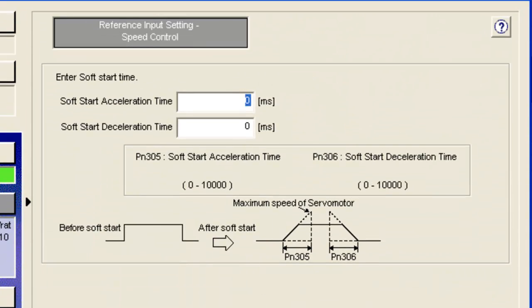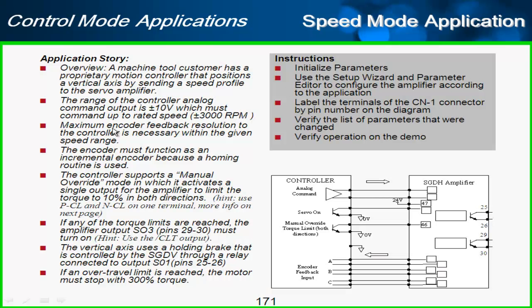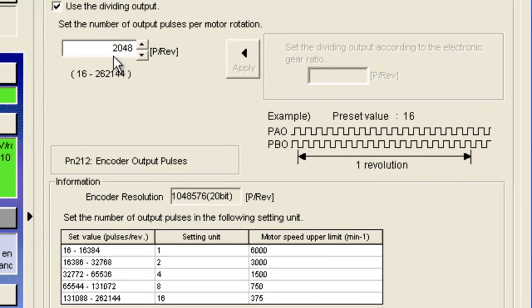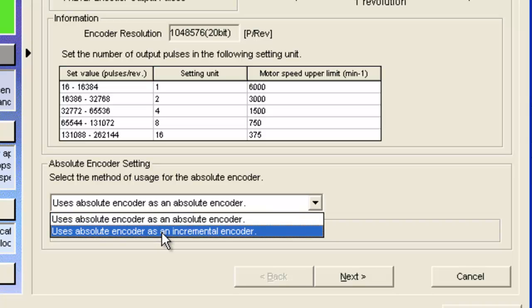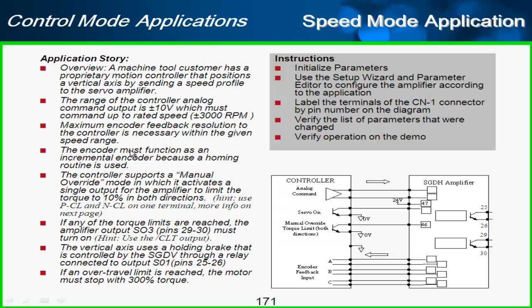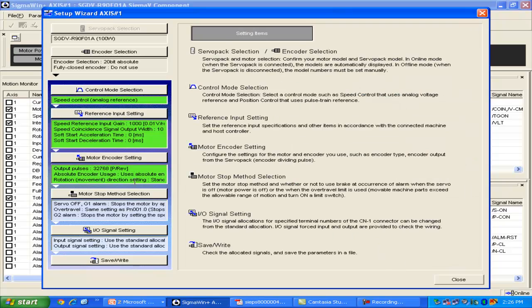There was no mention of a speed coincidence or V-comp output, so I'll click next. There was no mention of any acceleration times, so we'll leave those at default. On to motor encoder setting — this is the number of pre-quadrature output pulses per rotation. The application requires maximum resolution within the 3,000 rpm speed range, so the maximum is 32,768. I'll also choose to use the absolute encoder as incremental, as specified. There was no mention of reversing direction, so I'll leave that at default.